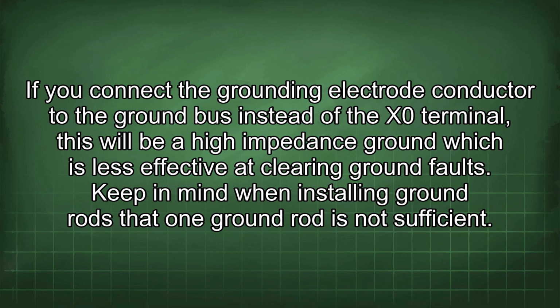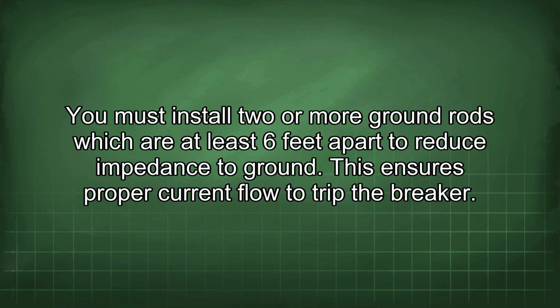Keep in mind when installing ground rods that one ground rod is not sufficient. You must install 2 or more ground rods which are at least 6 feet apart to reduce impedance to ground. This ensures proper current flow to trip the breaker.